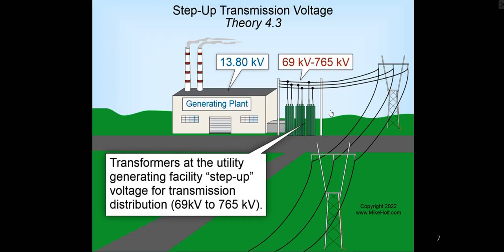That was the issue, going back a little bit, with Edison and Tesla and creating the electrical system that we know today. Edison wanted to use DC, and if we would have used DC, you'd have to have a booster station or a substation every mile or so. Whereas with alternating current, you can boost it up and transmit it for long distances and then drop it back down to the usable voltage once it got closer to where you wanted it to be.